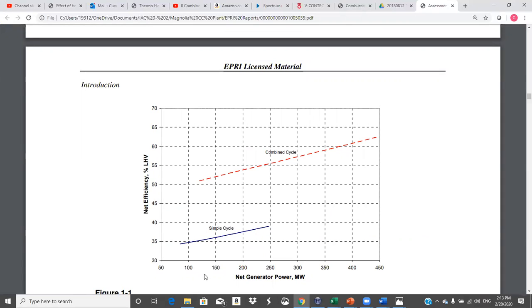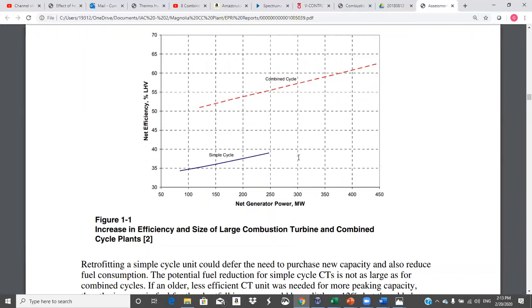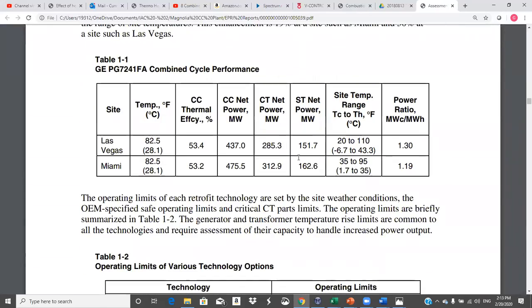And so you see, based on the megawatts, the efficiency increase. At say 200 megawatts, this simple cycle is maybe 37.5% efficient. A combined cycle is about 54% efficient. So that's why you buy that heat recovery steam generator and the steam turbine, put the whole steam Rankine cycle, and team it up together. And of course, then you can get larger and larger capacities. Those TVA units out here were about 300 megawatts, so they were probably 57, 58% rated efficiency. And there's all kinds of stuff in here.